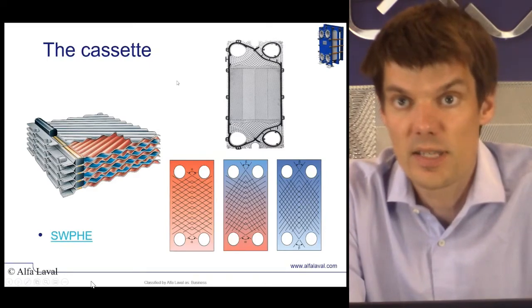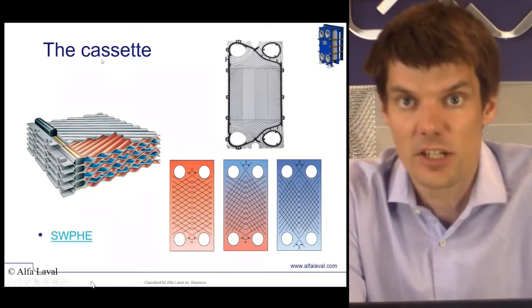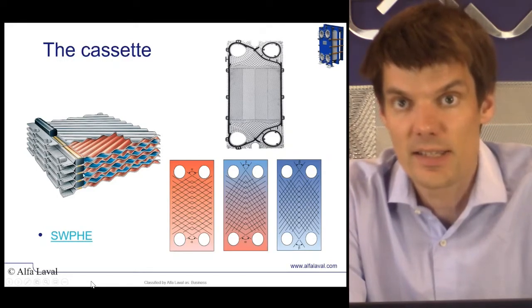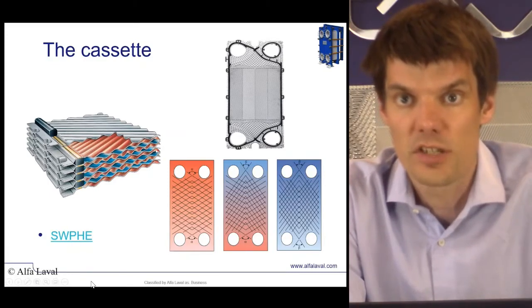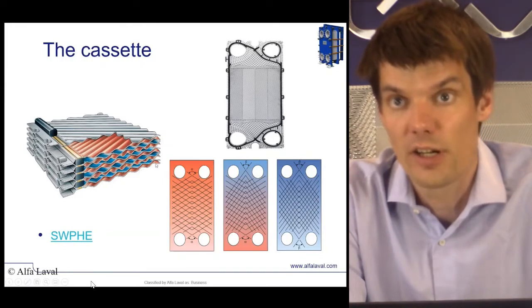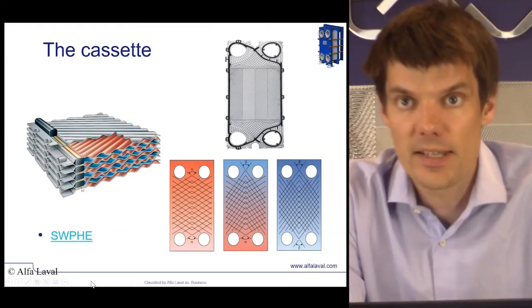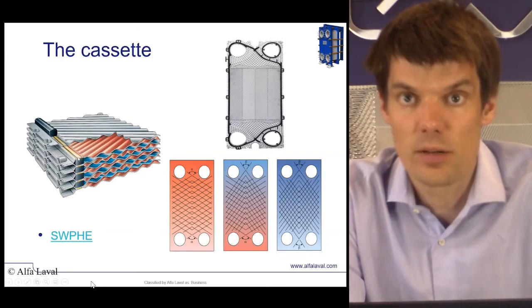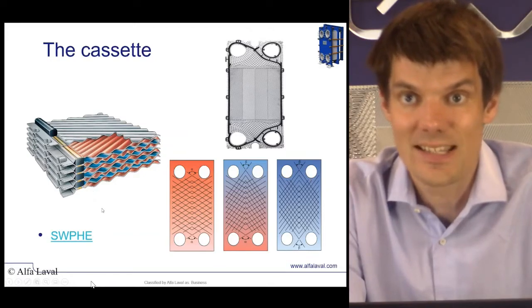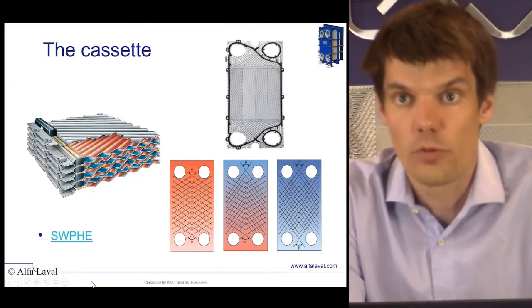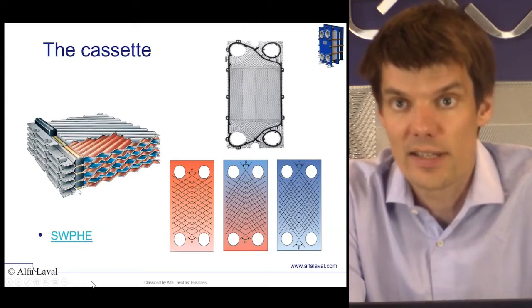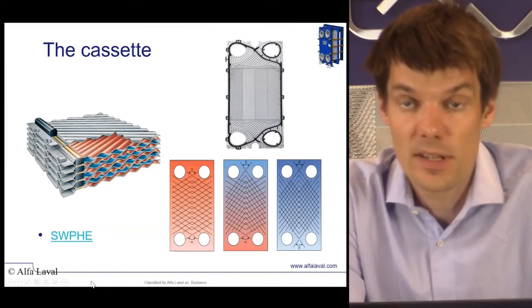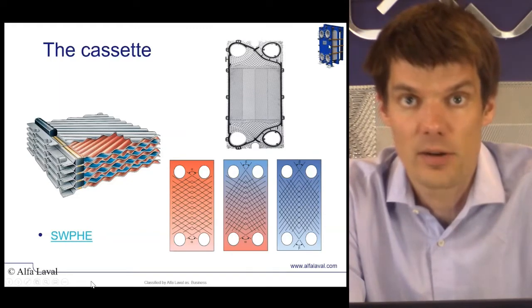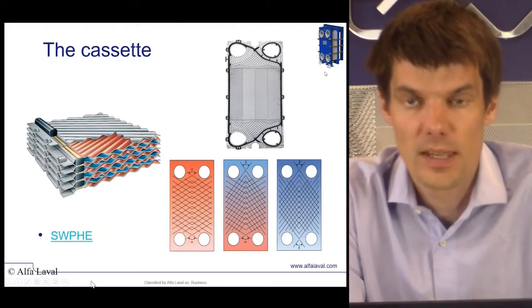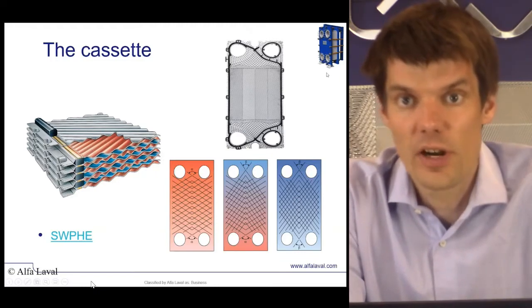The difference between a semi-welded plate heat exchanger and a standard gasket plate heat exchanger, where all plates are sealed off with the gasket, is that in a semi-welded plate heat exchanger, every second plate is welded together to form a cassette, which gives a very strong heat exchanger channel with a smaller gasket exposure. The cassettes are then stacked together and sealed from the outside with the field gaskets, which help to form the so-called gasketed or field side, and the ring gaskets, which form the intersection between the welded side, and then put onto a frame, looking like something we have up here in the top right corner. This in all gives a heat exchanger with a very good performance.